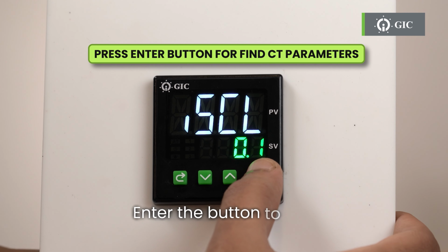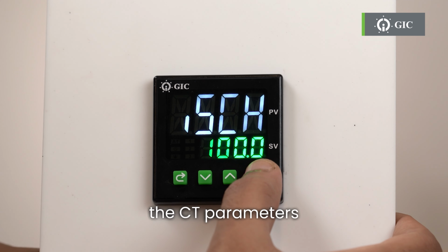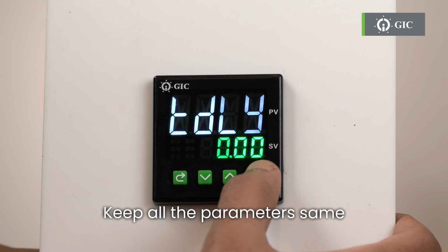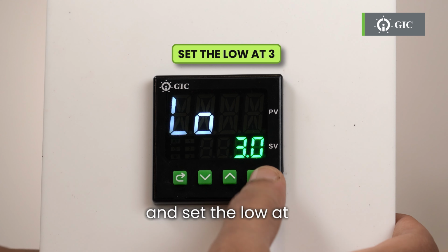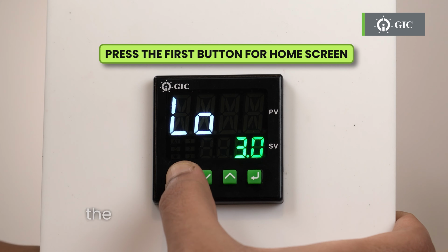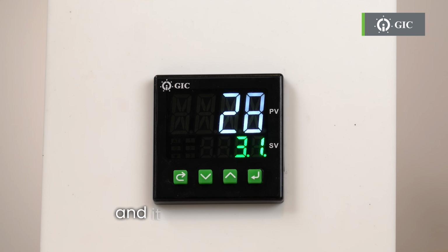Enter the button to find the CT parameters. Keep all the parameters the same and set the low at 3. Come back by making use of the first button to the home screen, and it is on until the current is below 3 and it turns off after the current rises above 3.